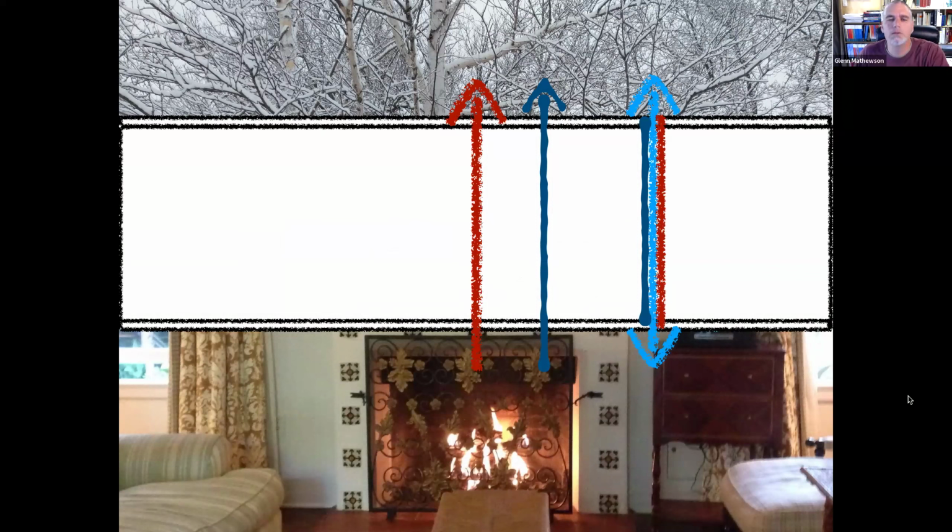The heat can just pass right through. That's the red line. The blue line is water vapor in air form, just passing and diffusing through these solid materials. Okay, so that's vapor diffusion going through the materials. And then the third line, the light blue line, is the air that could pass through these. And remember, the air is going to bring both temperature and a relative humidity with it as well. You can move humidity through diffusion through solid materials, a much slower method of moving humidity, or you just move it directly on the air.